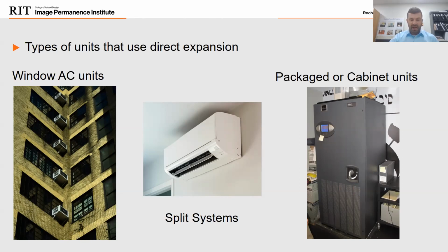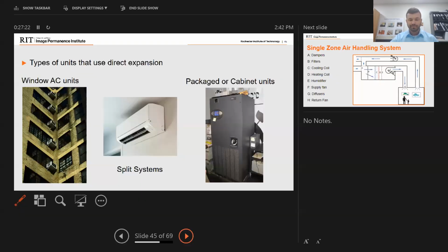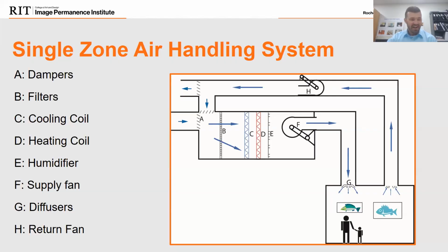So here is back to the example that I discussed originally. We crashed. Yep, no, we didn't. So back to the unit we discussed originally, the single zone air handling system. This was that basic unit I explained earlier, where we're going to return that air, we're going to exhaust some of it, we're going to filter some of it, and then we'll pass it through the heating, the cooling coil, or cooling and heating coil, I'm sorry, and exhaust it into the space.